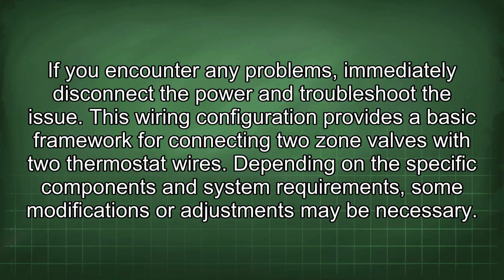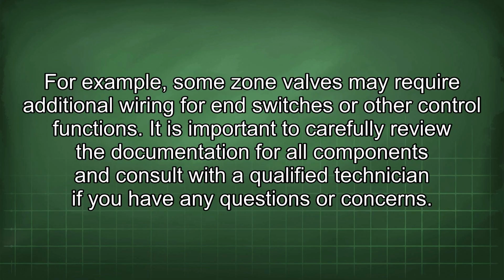This wiring configuration provides a basic framework for connecting two zone valves with two thermostat wires. Depending on the specific components and system requirements, some modifications or adjustments may be necessary. For example, some zone valves may require additional wiring for end switches or other control functions. It is important to carefully review the documentation for all components and consult with a qualified technician if you have any questions or concerns.